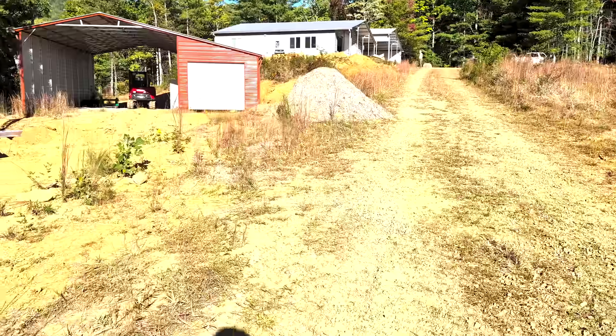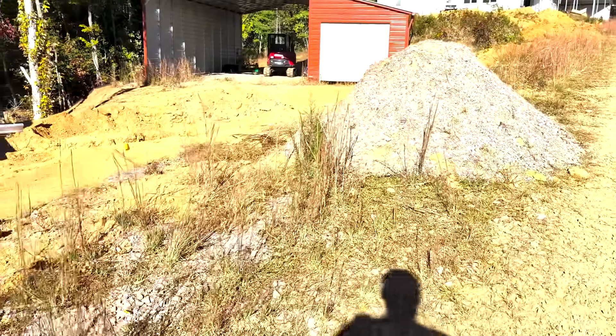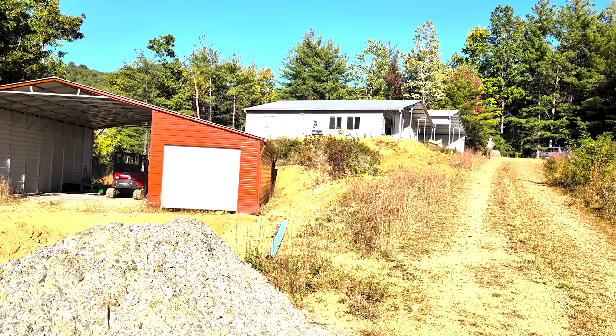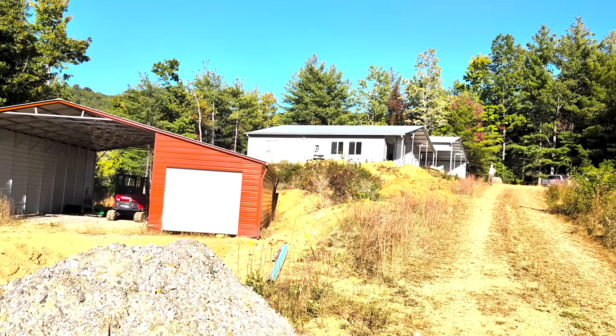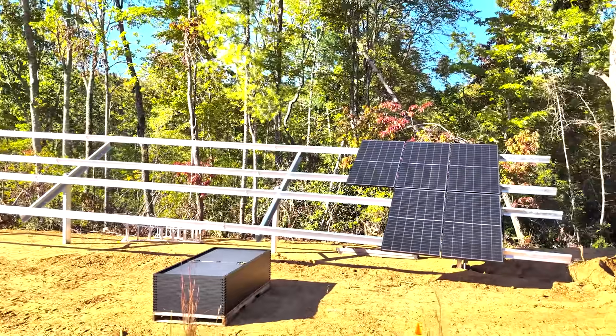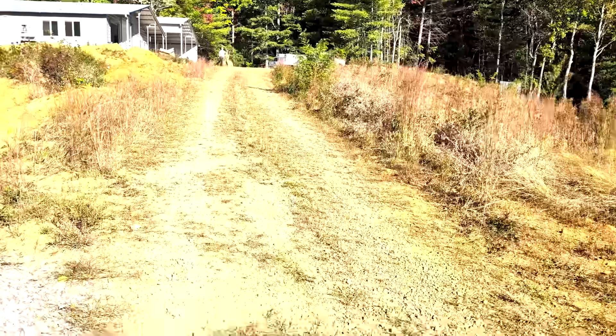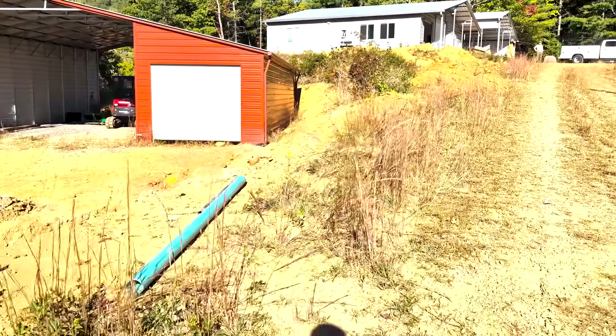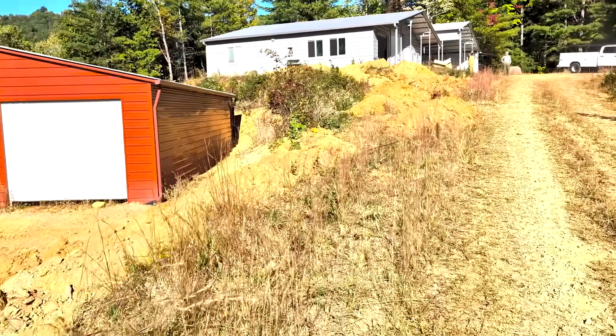We had to cross the septic twice, a water line, a well power line — and we found everything before we tore it out. So that's a good day. Everything's run up to that outdoor panel. We're going to put a bypass which will serve as a disconnect. Everything's off-grid here — there's no utility. So we're going to use a double-pole, double-throw disconnect that will shut power off to everything, and he can lock it if he wishes. We made progress. Might not look like it because it's mostly underground. Got our outdoor gutter perpendicular with our indoor gutter. We'll build the battery bank and we'll be in business tomorrow.